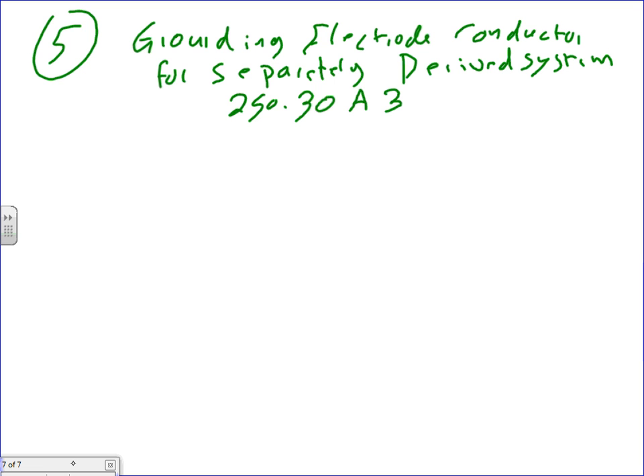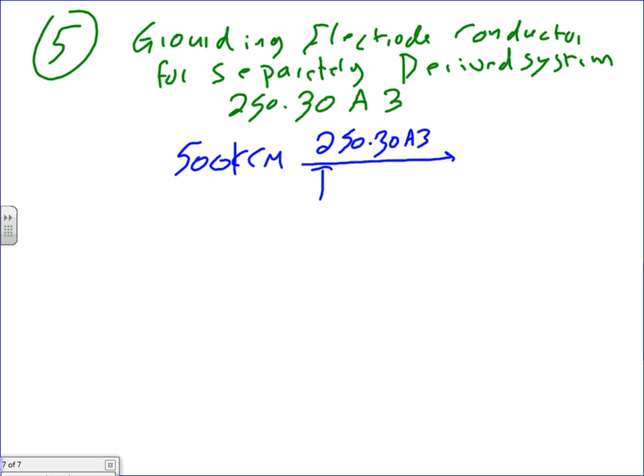Okay, go to that section and it will tell you the following. What was the conductor feeding this? How many conductors? 500? Okay, let's take the 500 kcmil. Take this to 250.30(A)3, and it refers you to Table 250.66. Can you go there and size it? The 500 are the conductors on the secondary side of the transformer.